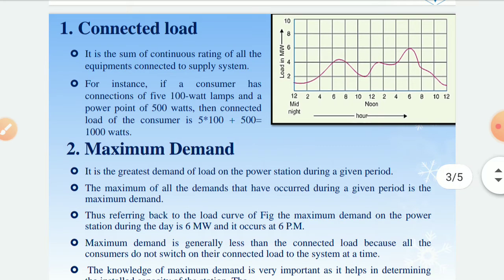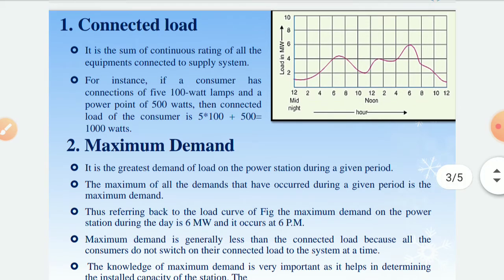The first term is connected load. It is the sum of continuous ratings of all the equipments which are connected to the supply system. For easy understanding, I will explain it using our home. If you have different equipments at home and you add all the ratings of those equipments connected, then the total value is known as the connected load. For instance, if a consumer has five 100-watt lamps and one power point with 500 watts, then the connected load is 5×100 + 500 = 1000 watts.